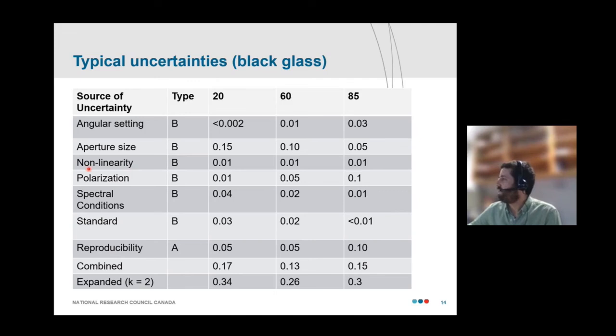I didn't say much about the non-linearity, but the way we deal with that is we have a facility for measuring the linearity of a photo detector. And so, we basically have done that with the photomultiplier tube used in the instrument. And then we ensure that we stay in a linear regime of photocurrents where the residual non-linearity is thought to be quite small.